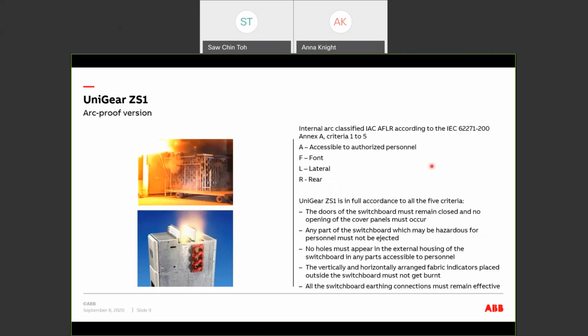UniGear panels are internal arc proof. They are tested to IEC 62271-200, Annex A, and fulfill all 5 criteria, so it is classified as IAC AFLR. A means only accessible to trained or authorized personnel, and FLR shows the area that is protected. If the operator is standing at the front, at the sides, or at the back of the switchboard, they will be protected in the event of an internal arc fault.